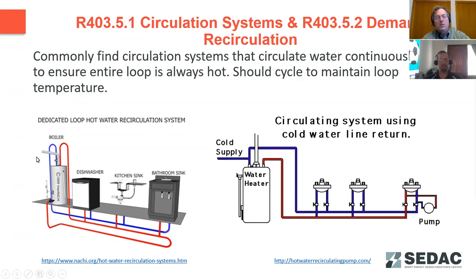For the circulation system, that's a dedicated hot water loop. Usually that flow sensor is going to be on the inlet line to the hot water tank, because as you're drawing hot water out of that tank, you're going to be drawing in cold water to refill it, and that's going to be your identification of hot water demand in the building.